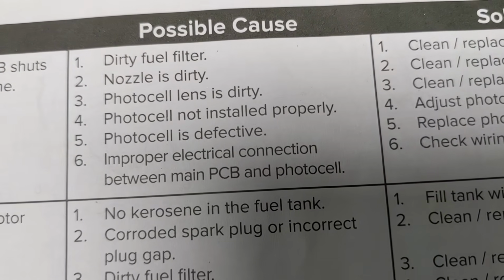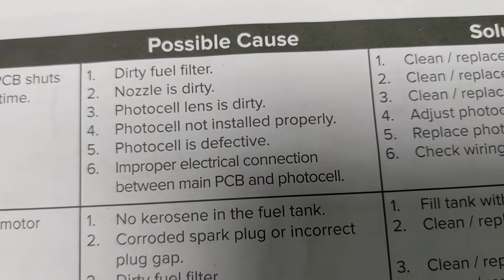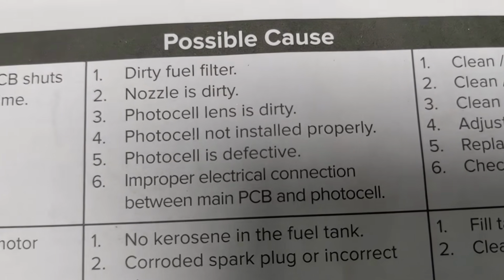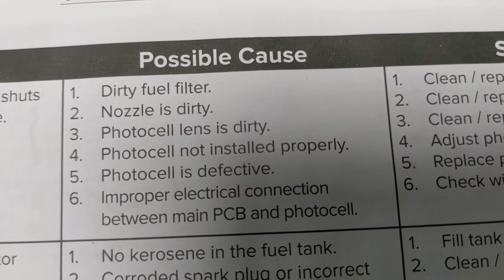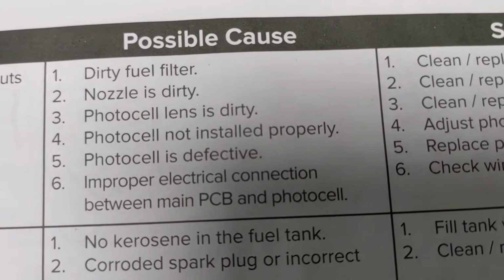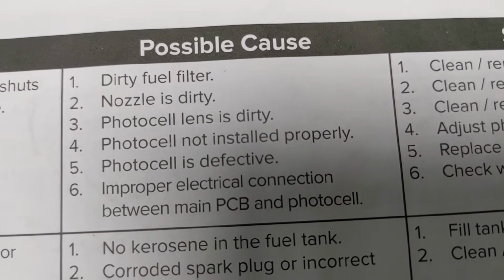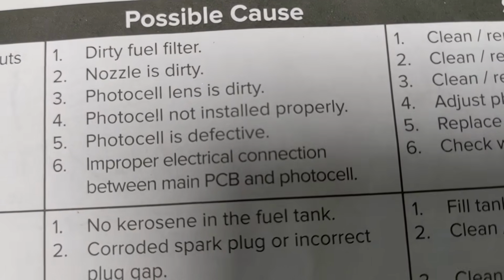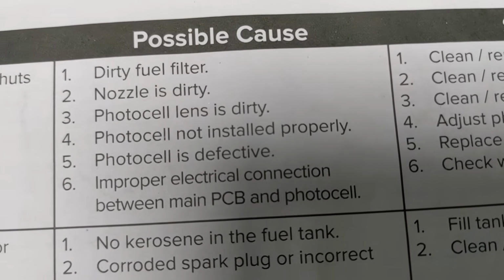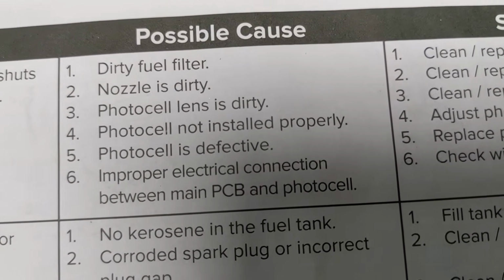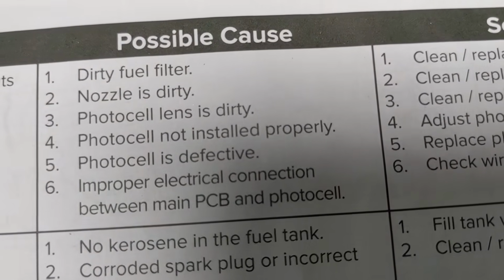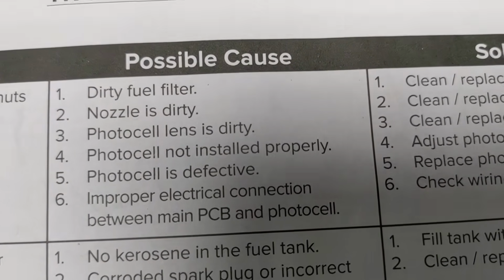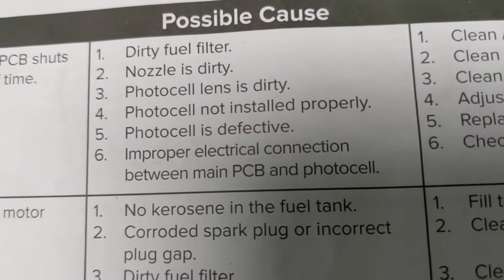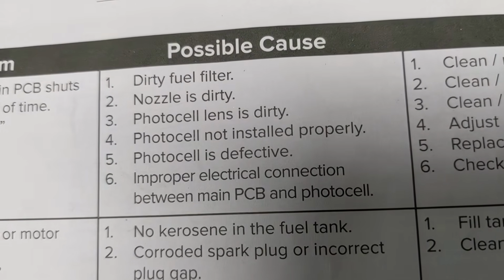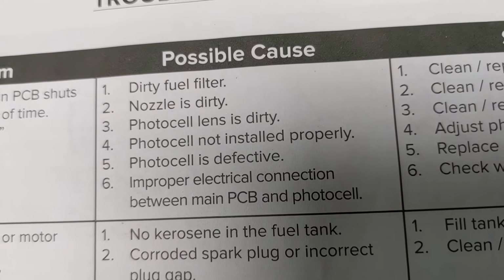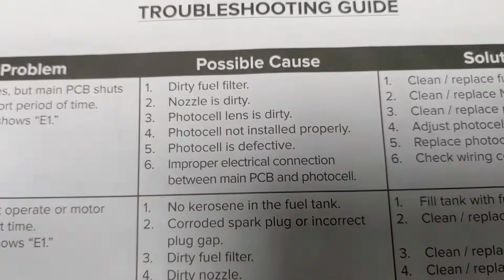I made sure it was lined up correctly. I also tried to run the machine and bypass the photocell by shining a flashlight directly in it, so I knew that it was registering that it sees the flame, and therefore that wouldn't be the cause of it shutting off. That didn't make it run. Still code E1. So photocell not installed properly or lens is dirty, neither one of those. Photocell is defective, no. All 3 bench test, fine. Improper electrical connection between the main circuit board and the photocell, no. I checked it. No corrosion, no nothing.